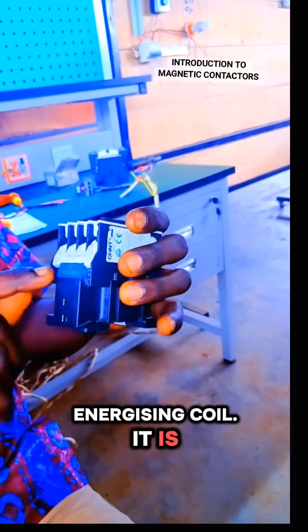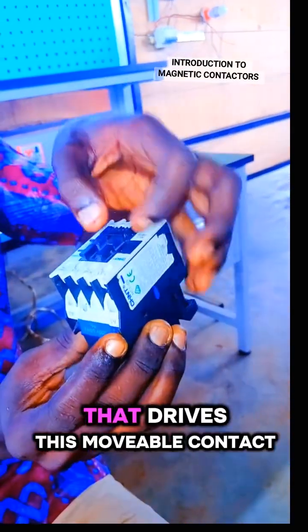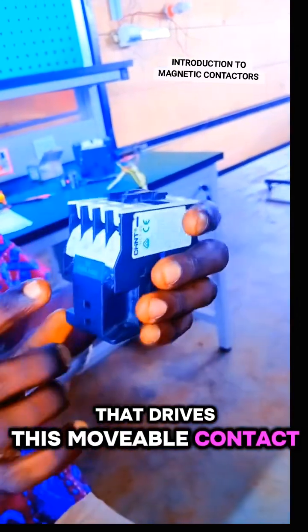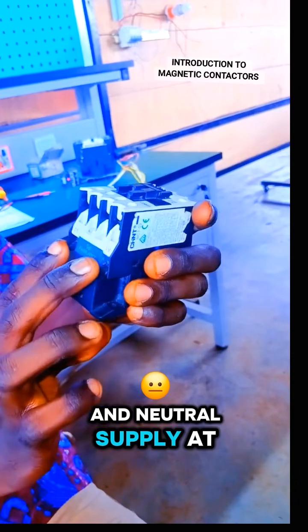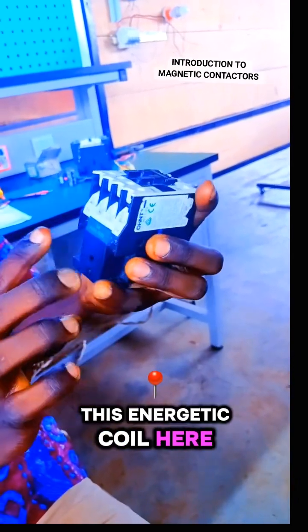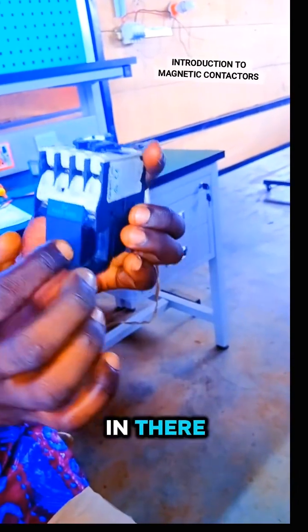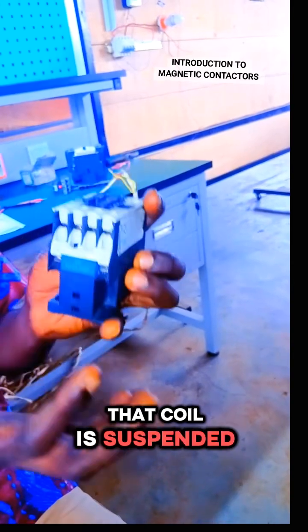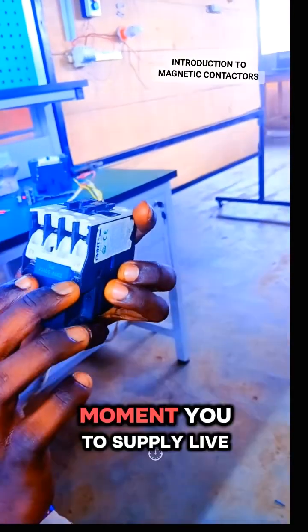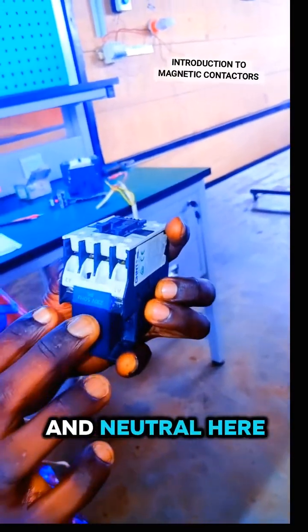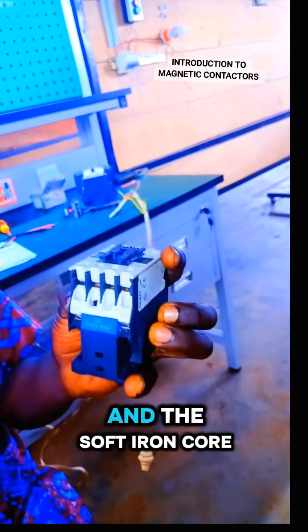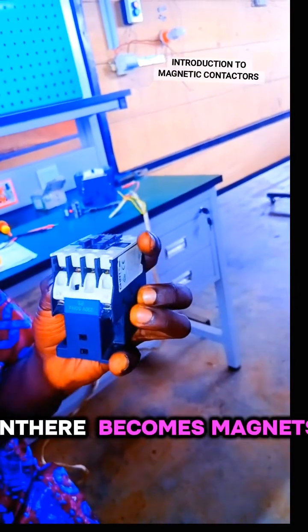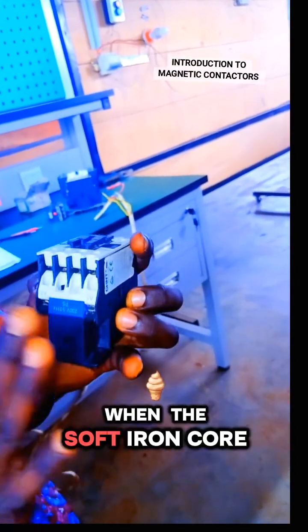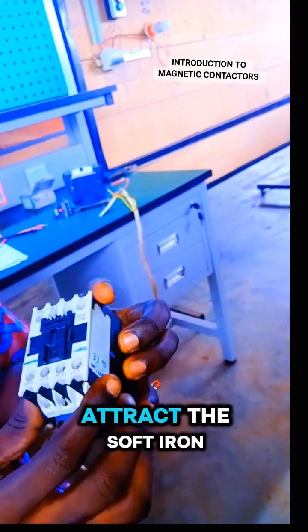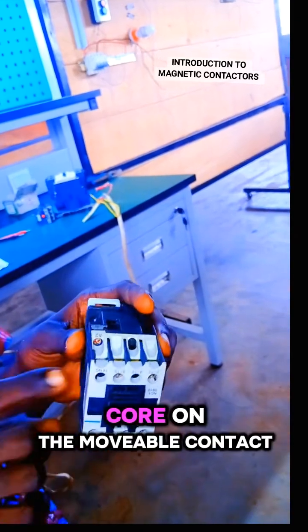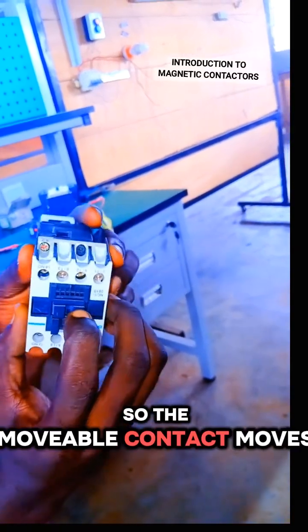It is the energizing coil here that drives this movable contact. If I put live and neutral supply at this energizing coil, there is a coil in there. That coil is suspended on a soft iron core. The moment you supply live and neutral here, the coil carries current and the soft iron core in there becomes a magnet. When the soft iron core becomes a magnet, it is going to attract the soft iron core on the movable contact. So the movable contact moves and closes.